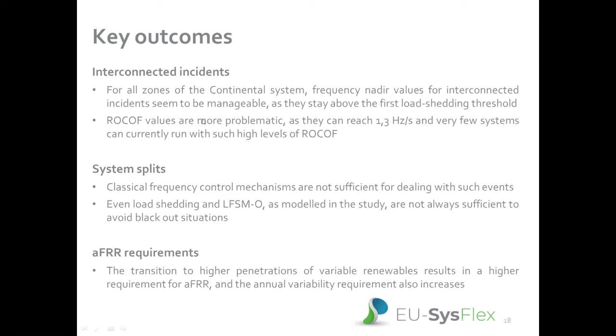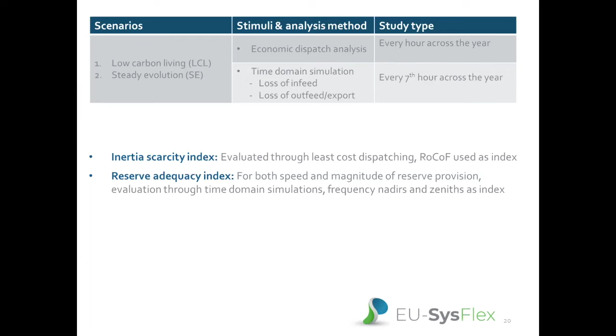Frequency stability and control analysis was carried out for the all-island power system using 2 scenarios. 2 types of analysis were carried out: one was economic dispatch analysis, followed by time domain simulations. The analysis aims at investigating inertia scarcity through least cost dispatching analysis using rate of change of frequency, or RoCoF, as an index. This is followed by reserve adequacy analysis based on time domain simulations, whereby both speed and magnitude of reserve provision is evaluated using frequency nadirs and zeniths as indices.